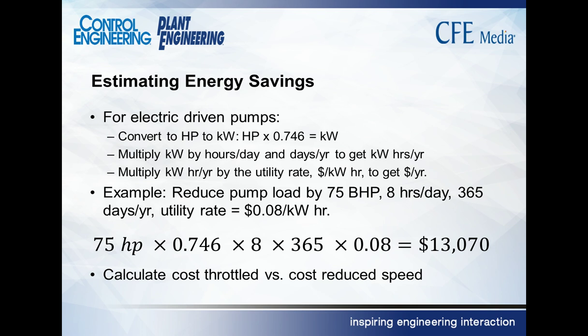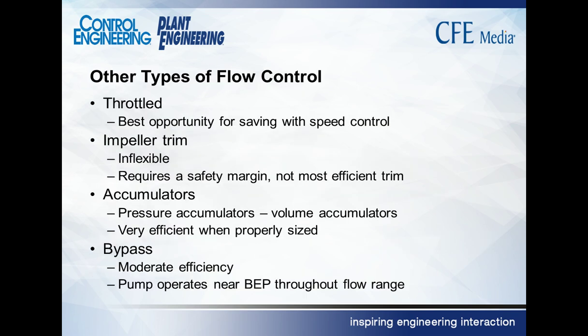Energy savings can be quite significant. This is an actual case from quite a number of years back. They were only paying 8 cents a kilowatt hour, a pretty good utility rate, but they eliminated 75 horsepower of load by adjusting this pump speed and getting it running close to its best efficiency point. It ran 8 hours a day, 365 days a year, one shift all year long. $13,000 in savings. Can be very significant.